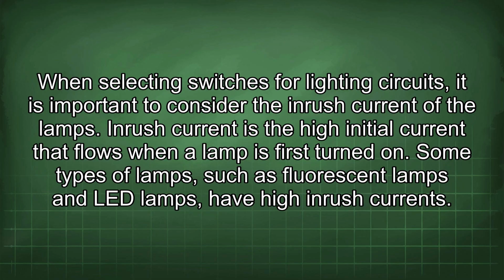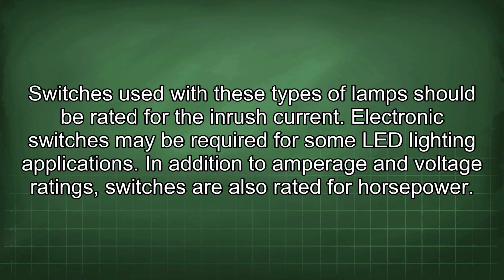When selecting switches for lighting circuits, it is important to consider the inrush current of the lamps. Inrush current is the high initial current that flows when a lamp is first turned on. Some types of lamps, such as fluorescent lamps and LED lamps, have high inrush currents. Switches used with these types of lamps should be rated for the inrush current. Electronic switches may be required for some LED lighting applications.